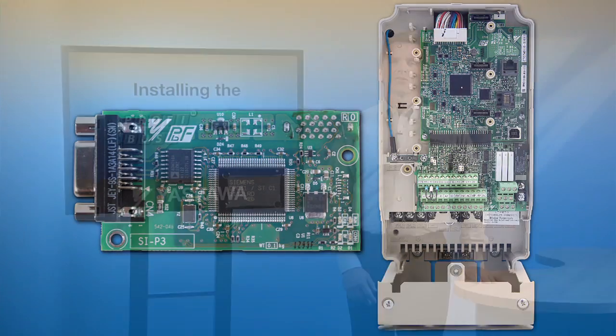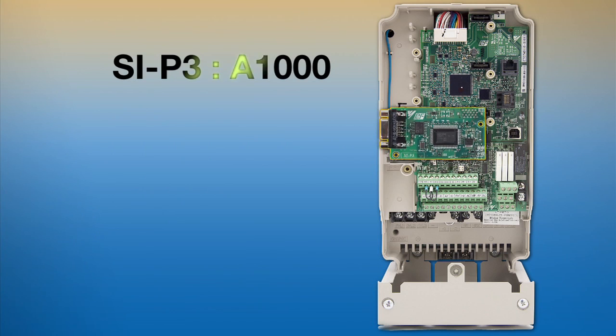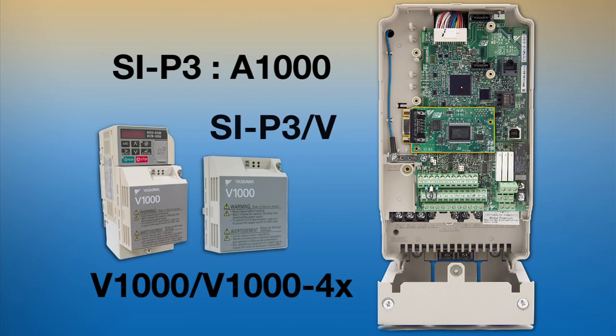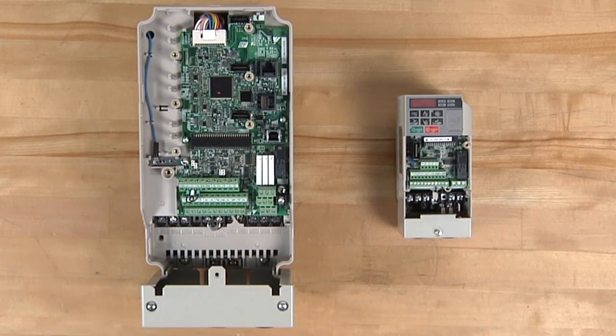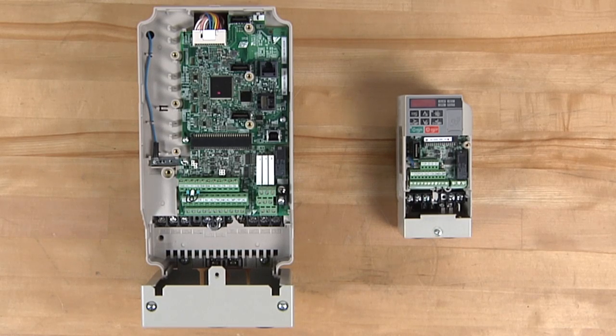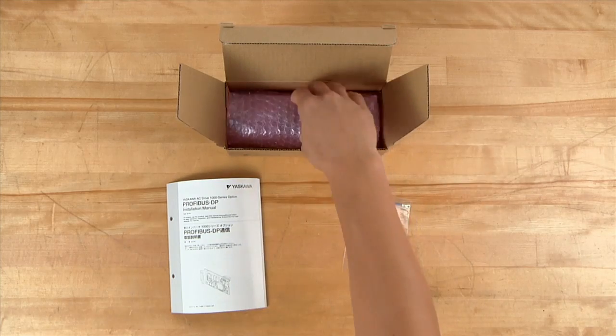A communication option card will be necessary if you want to network a Yaskawa drive with PROFIBUS. The SI-P3 option card is needed for an A1000 drive, and the V1000 and V1004X drives require an SI-P3/V option card. The option card plugs into the CN5A connector on the A1000 drive, and the CN5 connector for the V1000 and V1004X. The option card kit contains the PROFIBUS interface board, along with ground wires that should be attached to the earth ground terminal of the drive.